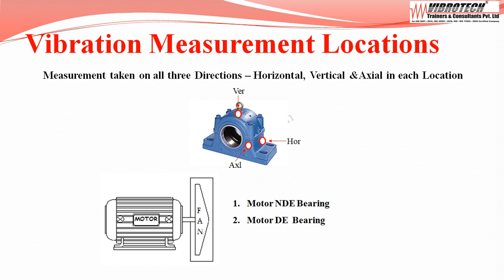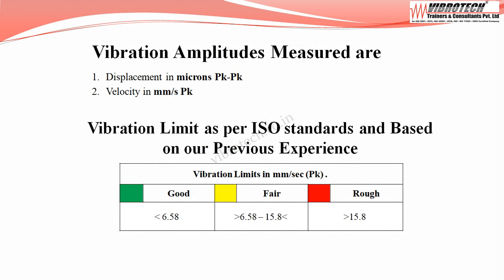Vibration measurements are taken in all three directions — horizontal, vertical, and axial — at each location. Measurement locations are the motor non-drive end bearing and motor drive end bearing. Vibration data are collected in terms of displacement in microns peak-to-peak and velocity in mm per second peak.